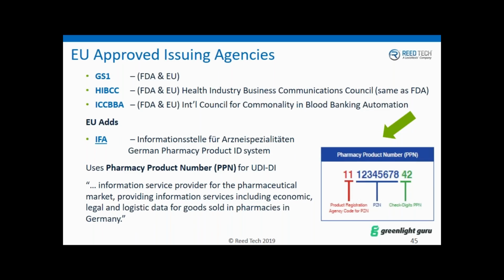Quickly, let's move over to the approved issuing agencies. The first 3, if you've been working with the FDA, you'll recognize them: GS1, HIBCC, and ICCBBA. Noteworthy is the addition of a 4th, IFA, and I will not try to pronounce this German pharmacy production identifier system, but there's a PPN that this system accommodates, and some structure here on the right. It's, as I understand it, used by pharmacies to identify medical products, including medical devices, and it was approved by the European Commission as the 4th issuing agency. So keep that in mind.